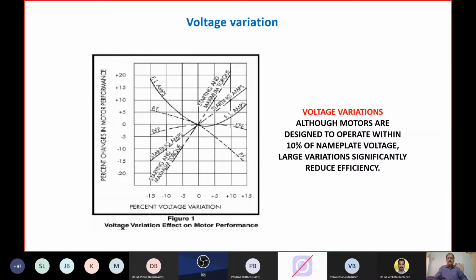Then the voltage variation, I have a commentary here. Although the variation permitted is plus or minus 10% or 15%, you can see here in this graph, 0 is the rated voltage, which is 415 in India. So anything on the negative side or on the positive side, the performance will vary. As you can see, full load ampere will be high as the variation increases, and also as the voltage decreases and variation increases, the ampere will increase. Similarly, power factor will change from one end to another end. But efficiency is the only factor which is affected on either side. The efficiency of the motor goes for a toss because of the voltage variation.